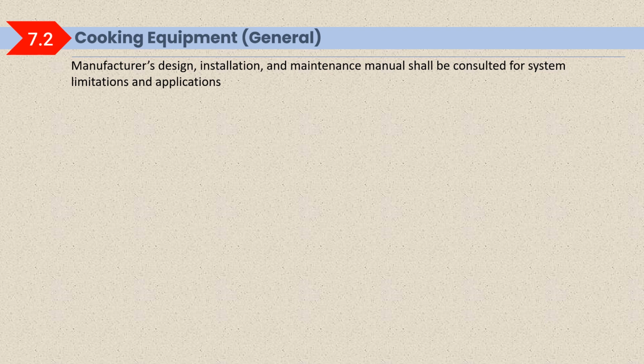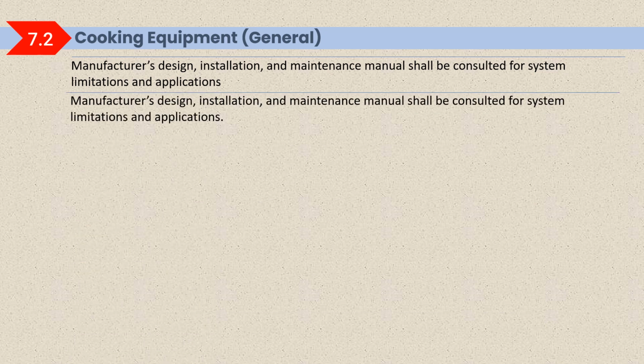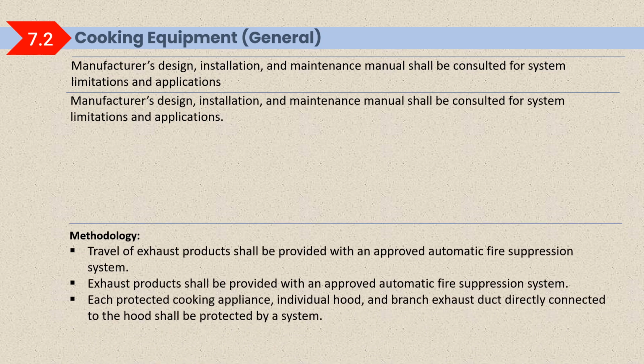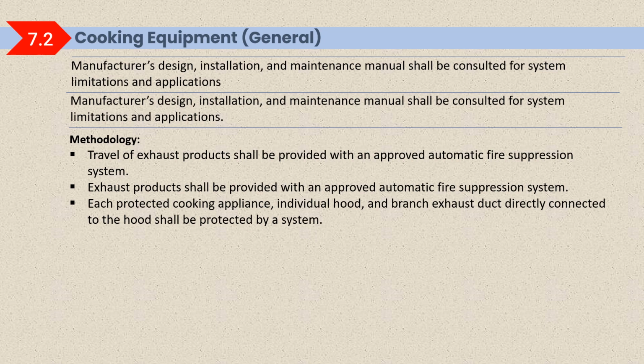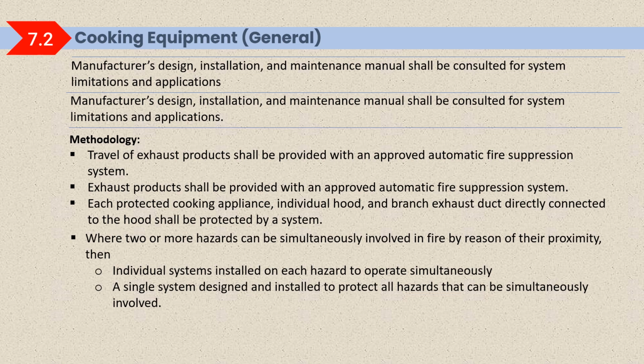Manufacturer's design, installation and maintenance manual shall be consulted for system limitation and application. So the manufacturer's guidelines or instructions should be used. The travel of exhaust products shall be provided with an approved automatic fire suppression system. Each protected cooking appliance, individual hood and branch exhaust duct directly connected to the hood shall be protected by a system. Where two or more hazards can be simultaneously involved in fire by reason of their proximity, then an individual system shall be installed on each hazard to operate simultaneously, or a single system shall be designed and installed to protect all hazards that can be simultaneously involved.